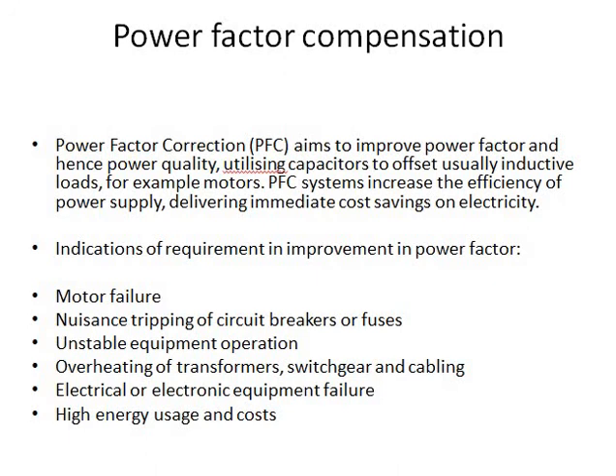It's not able to give its optimum performance. These may be the reasons, indications with respect to the motor, for need of power factor improvement. Further, nuisance tripping of circuit breakers or fuses can again be a very good indication to the technician, to the engineer, of the requirement of improvement in power factor.